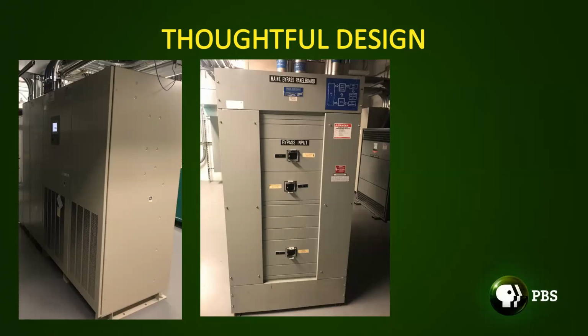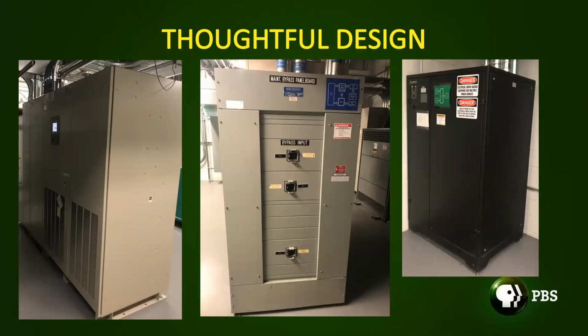There's another really nice device to have, and that's this. It's an STS, a static transfer switch. Now, we try to insist just as much as we can that every single device that we have in our facility is dual powered, has dual power supplies. That way we can put one power supply on power system A, the other power supply on power system B. So even if we lose one of our two power systems, that piece of equipment should continue running on the other power supply. The problem with that, of course, is that there are some devices that just don't offer the option of dual power supplies.